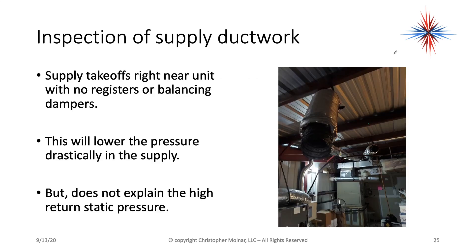Looking at the supply ductwork: I found supply takeoffs located right off the unit's supply plenum with no registers or balancing dampers. This is going to lower the supply pressure drastically — it acts like a big hole in the ductwork. However, it still does not explain the high return static pressure.